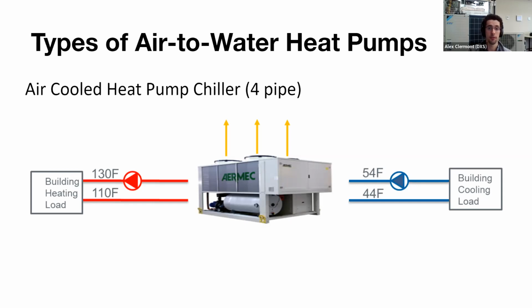These machines can also help with domestic hot water. They can't specifically do domestic hot water, but you're making hot water in your building, which can actually help to electrify your domestic. In terms of disadvantages for these types of systems, low ambient capability. Oftentimes you might still need a backup boiler for heating, and they can't really get close to what real air source heat pumps like VRF can do in terms of heating capacities and derates for heating. And this is a bit of an issue for cold climates as we're in here. So oftentimes these need to be designed with backup heating, extra boilers, and that's a big deal.